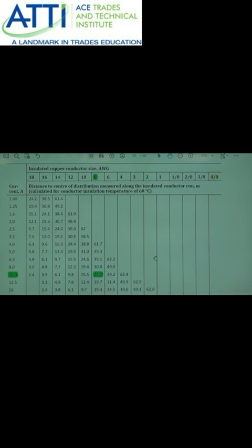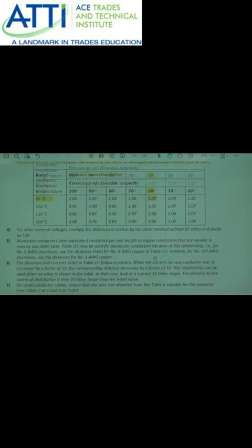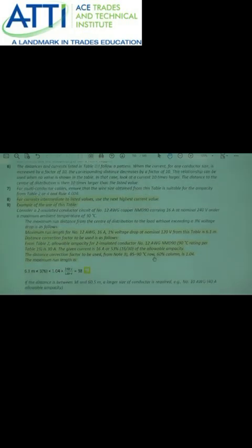What if I had 240 volt or 600 volt or whatever voltage might be? In that case, the code book says you're going to go all the way to the bottom of the next chart and follow note 9. Note 9 is nothing but an example given that if your drop was more than 1% and your voltage was, let's say, more than 120, you will follow this math to find an answer. So what I need my rock stars to do is follow note 9 and you're going to practice one question. So open up your binder.